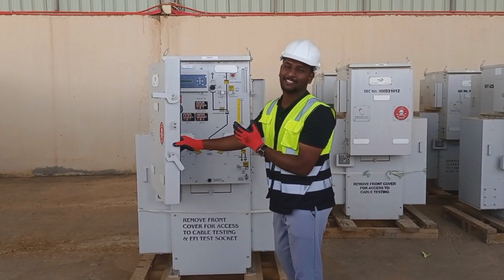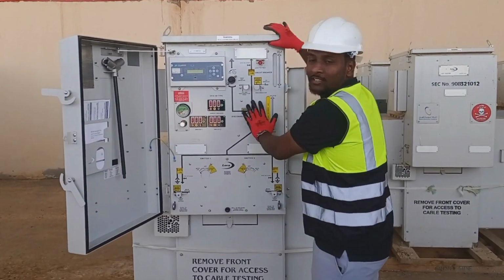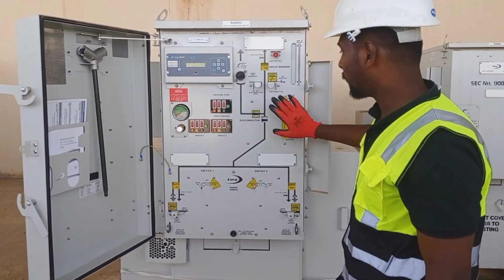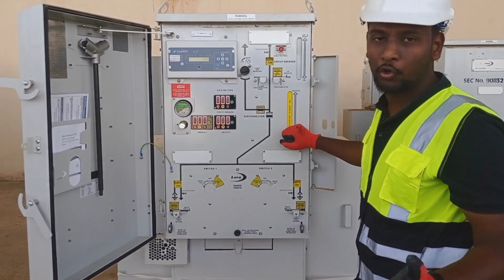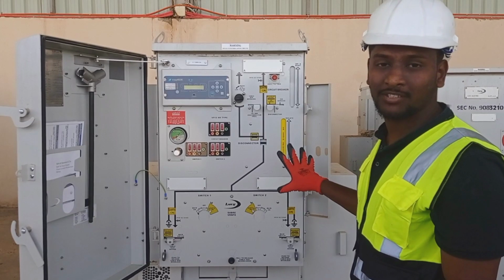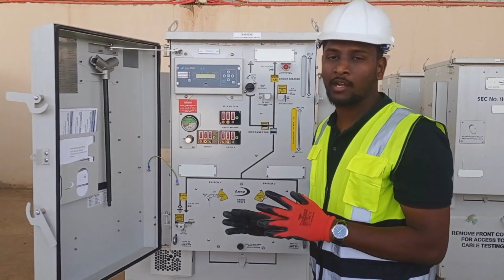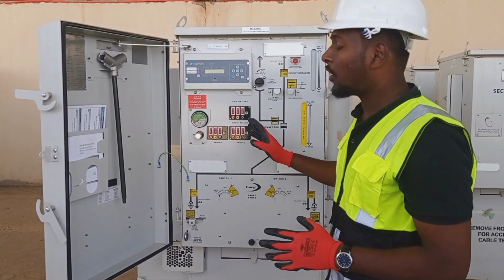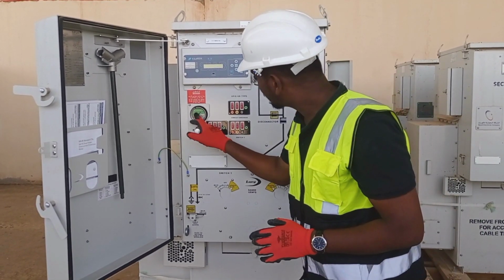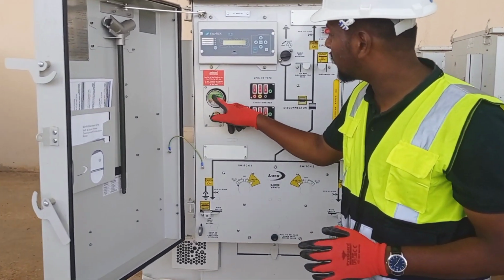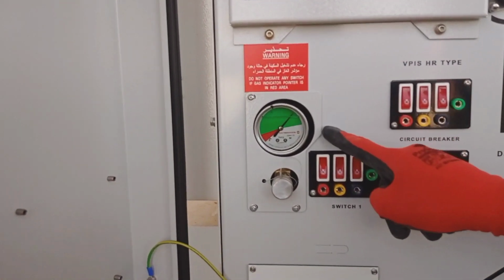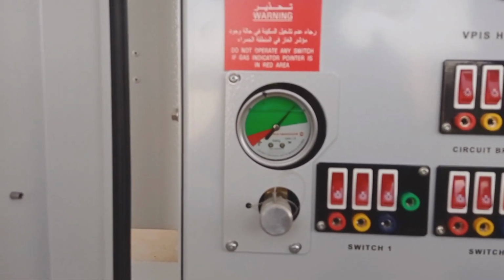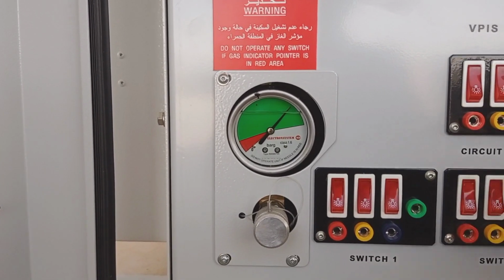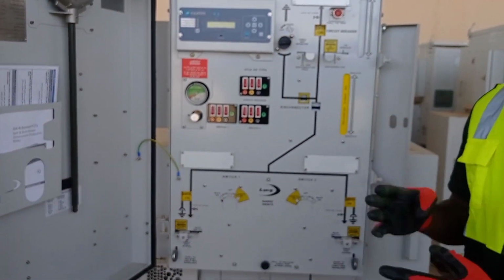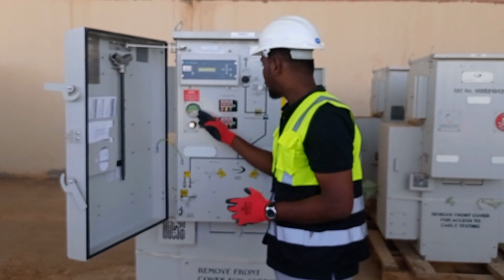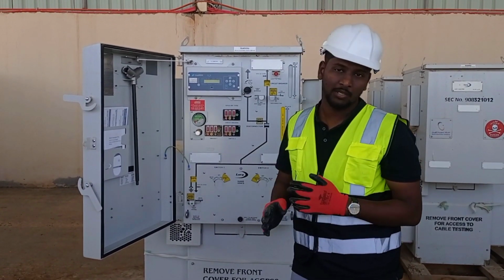Now we can see the inside of the RMU. This is how the inside of the RMU looks like. This is a three-way RMU, as I told you before, and it has many functions. First, whenever we are operating a ring main unit, we have to check the level of SF6. This is indicated by the SF6 gas gauge. SF6 means sulfur hexafluoride gas. It is used for protecting from arc. During operation, if any arc happens, it will be quenched. We are using SF6 gas as the arc quenching medium here.